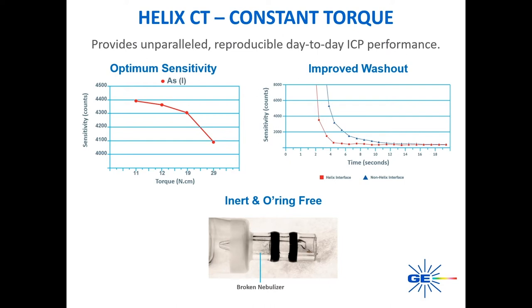The Helix CT interface is the standard option with all Glass Expansion spray chamber designs. It is also the only zero dead volume spray chamber interface available, providing superior washout especially for elements prone to carryover. Additionally, the Helix CT is a chemically inert seal, immune to strong acids and organic solvents, eliminating all drawbacks of O-ring seals. This also improves user safety by preventing broken glassware.